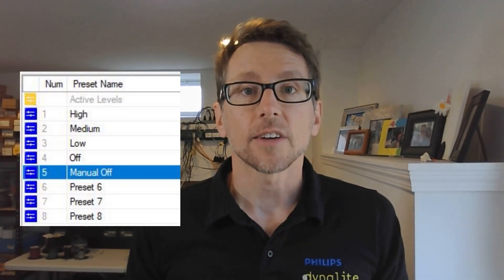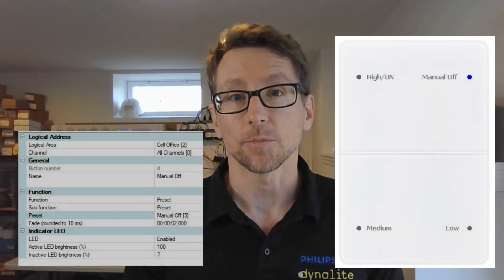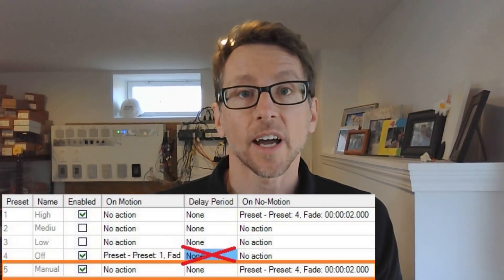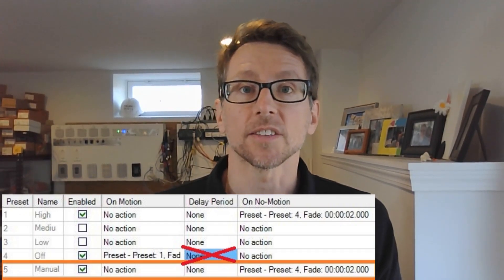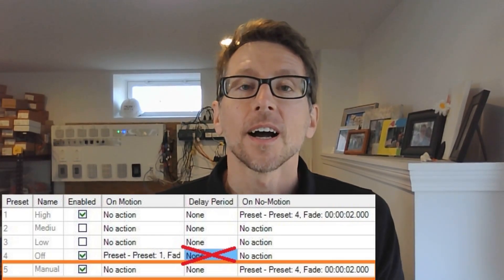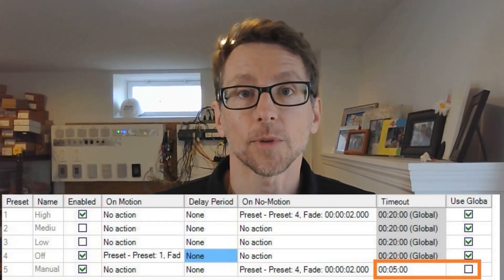Let's step it up a notch and really leverage all that flexibility. Sometimes, in a classroom or a meeting room, people want that magic of an occupancy sensor automatically turning the lights on, but they also want to be able to sit in the dark for a presentation. That's where a manual off comes in. First, we have to set up the manual off in the preset table. I've created a fifth preset called manual off where the lights are off. Then we configure our UI to send preset five instead of preset four for the off button, which then times out to preset four. That way, people can turn the lights off and sit in the dark. Lastly, we add our manual off to the motion table. We no longer need the action delay because now the UI is sending us to preset five, which then times out to preset four. Since we're never manually sending the lights to preset four, we don't have to worry about them turning on immediately. I personally like to have a shorter timeout on preset five so that if someone hits the button on the way out of the room, it doesn't take the full 20 minutes to refresh the occupancy.